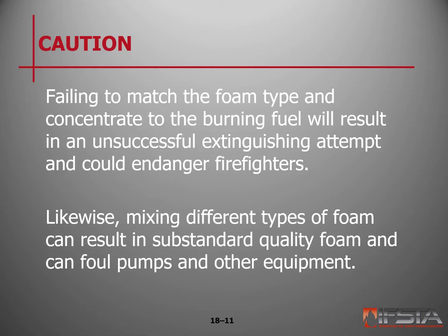A caution here: failing to match the foam type and the concentrate to the burning fuels will result in an unsuccessful attempt at extinguishment, and it could endanger firefighters. Likewise, mixing different types of foam can result in a substandard quality foam and can foul pumps and other equipment.